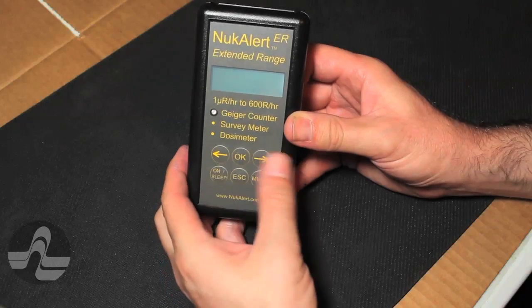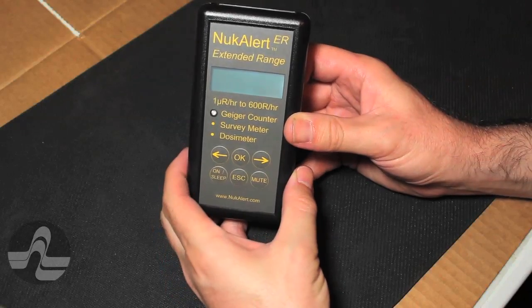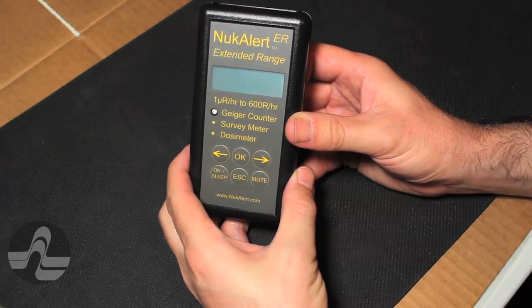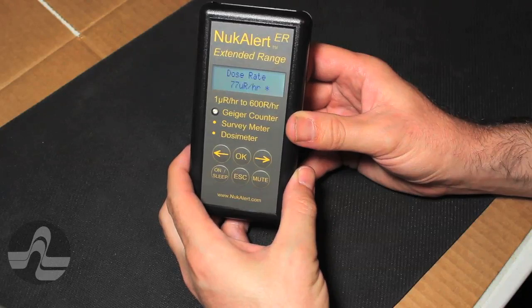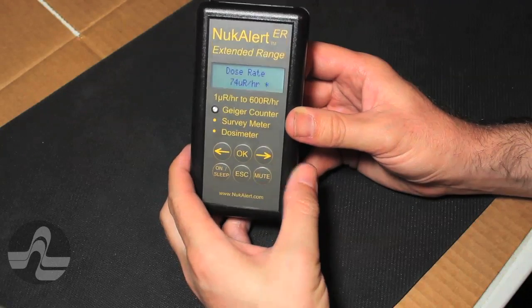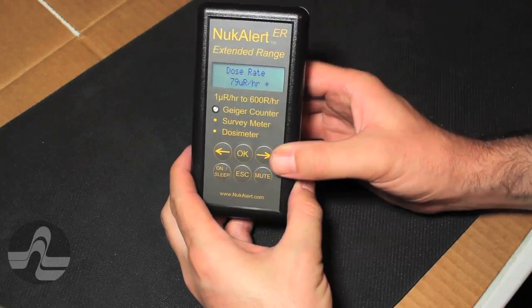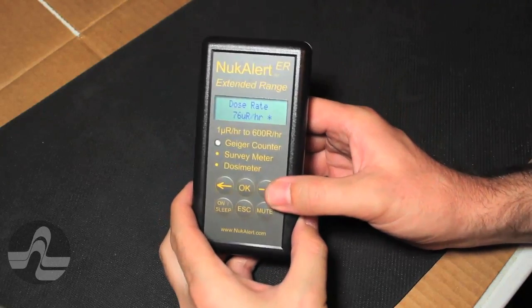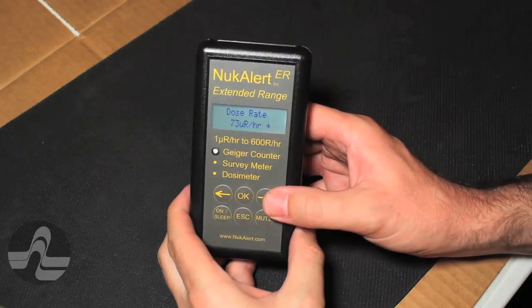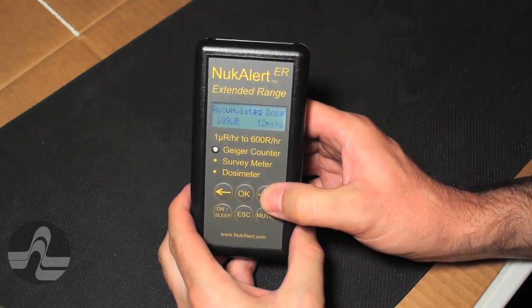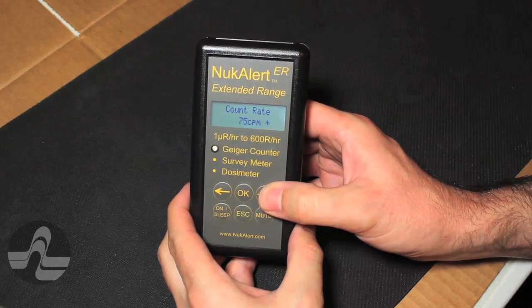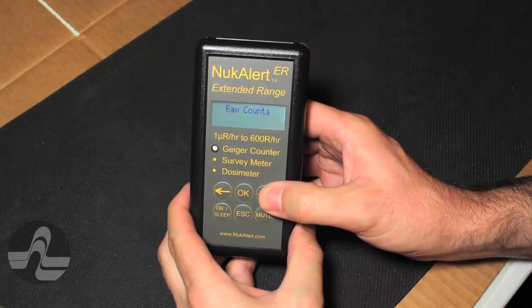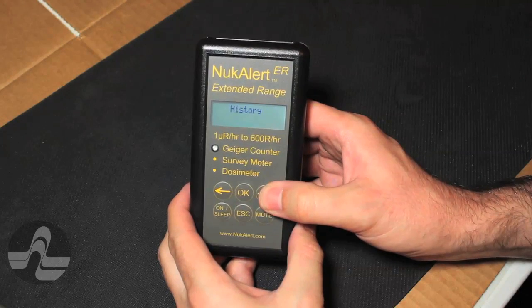Here is a quick look at the NukAlert ER. The root menu includes present rate, accumulated dose, approximate time until dose exceeds the current alarm threshold, count rate in CPM and CPS, long-term count totals, and history functions including browse and clear.